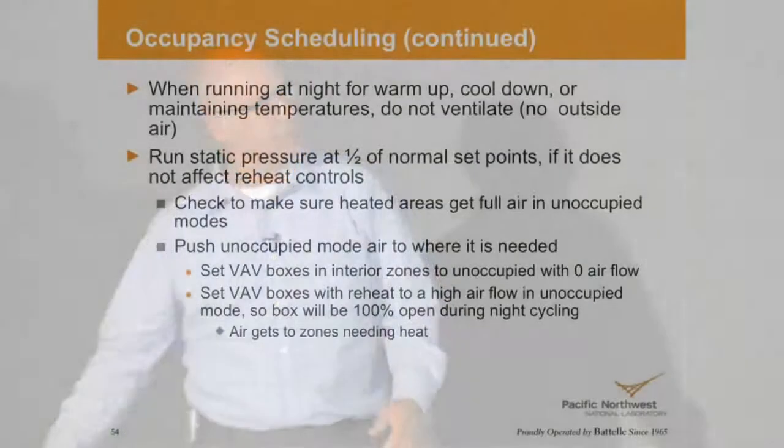How come the energy use for this building is so high? Oh, yeah, remember that weather event? Oh, we put everything in 24/7 override. Why don't you have your BAS automatically do it for you? So the operator doesn't have to worry about it, and then it will automatically take it out of that event and manage it for you. So that's something we would recommend if you're struggling with older buildings that are poorly insulated. You've got HVAC systems that are poorly maintained, because that's your kind of building, then guess what? You're probably going to be running 24/7 in extreme weather.